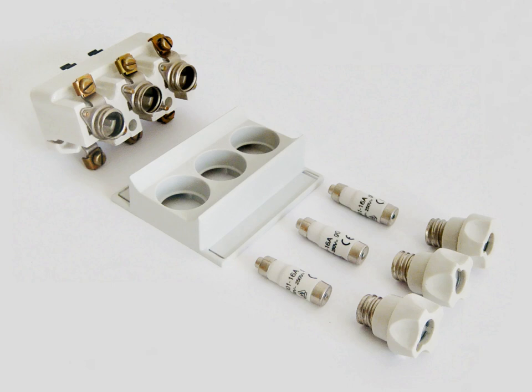The IEC standard unifies several national standards, thereby improving the interchangeability of fuses in international trade. All fuses of different technologies tested to meet IEC standards will have similar time current characteristics, which simplifies design and maintenance.